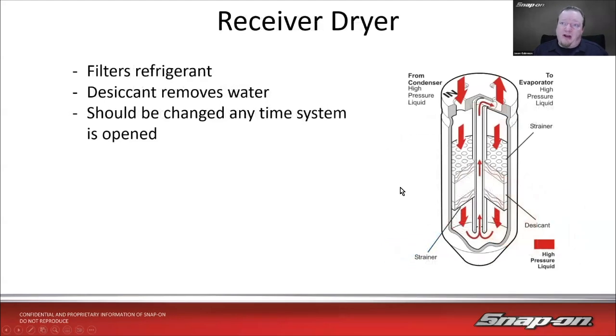The receiver dryer filters the refrigerant and contains a desiccant, which helps remove any water in the system. Hopefully there isn't any water in the system, but there may be. This should be changed out anytime the system is open, because as soon as it's cracked open, it introduces ambient water vapor from the air into the system. So I need to make sure that gets replaced, because that'll mess up the desiccant.